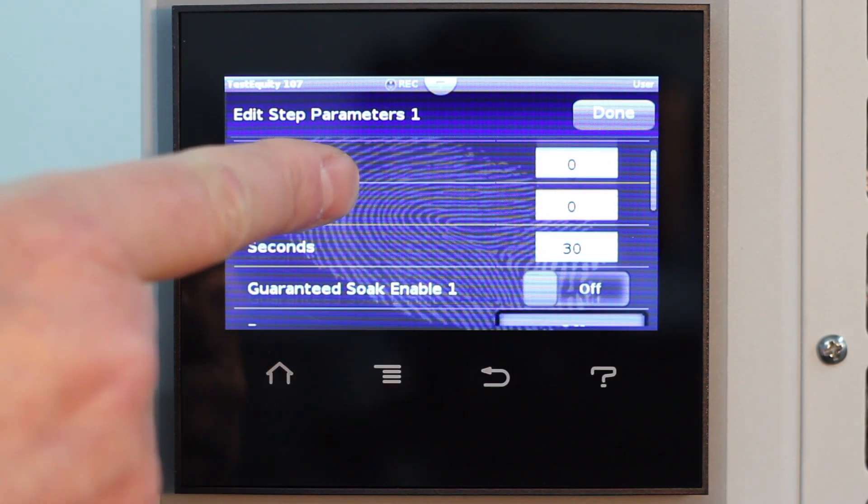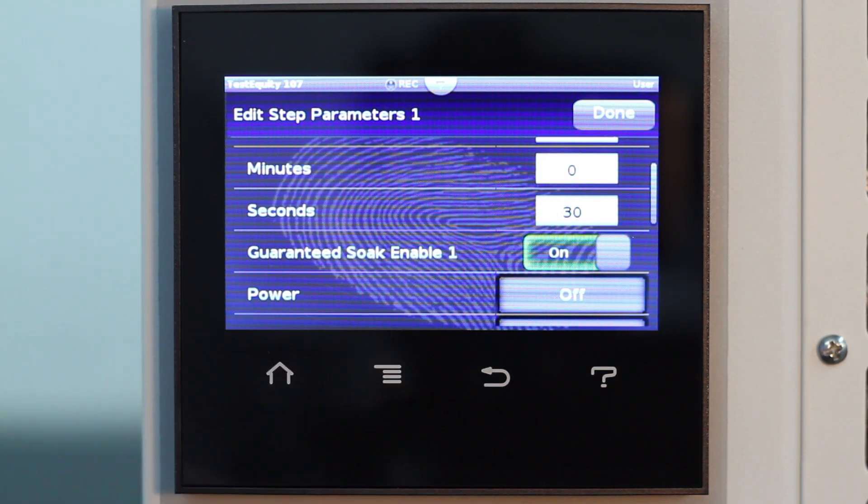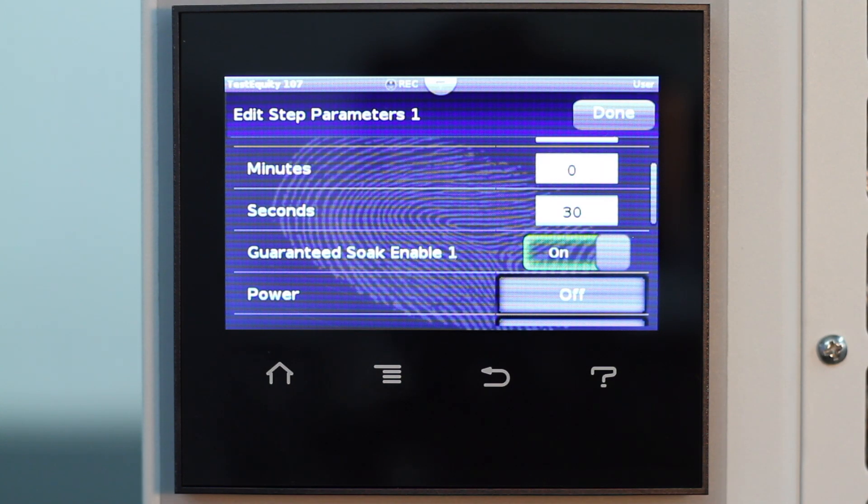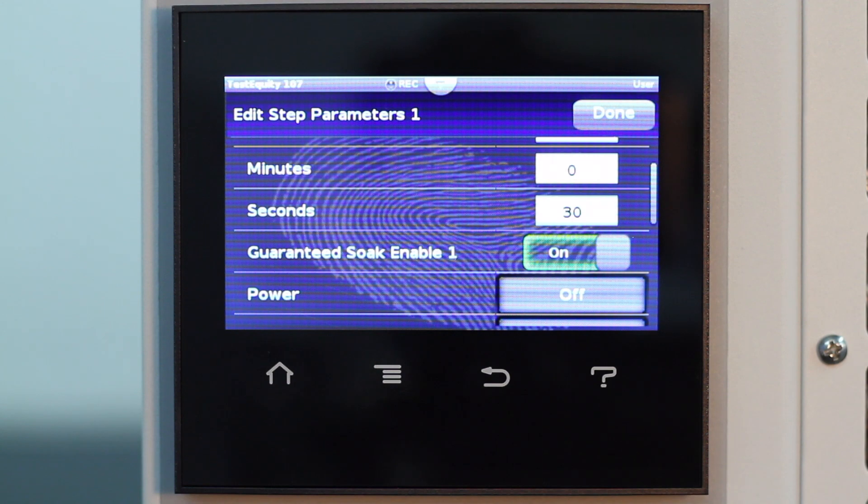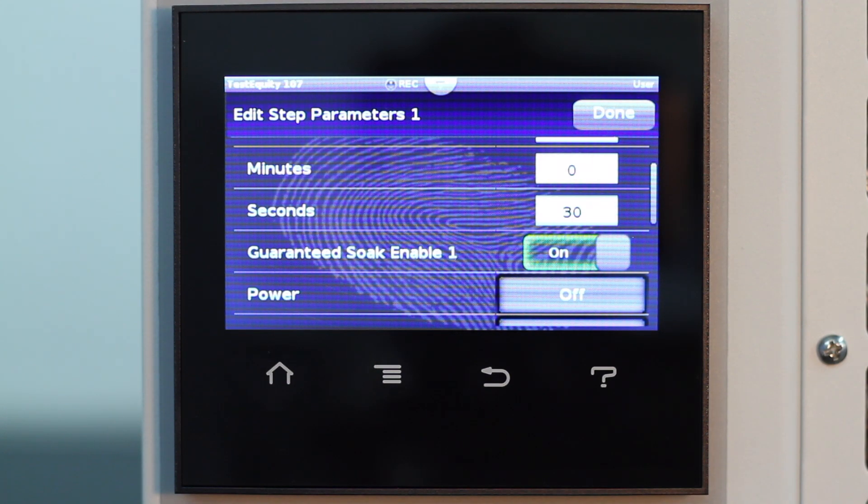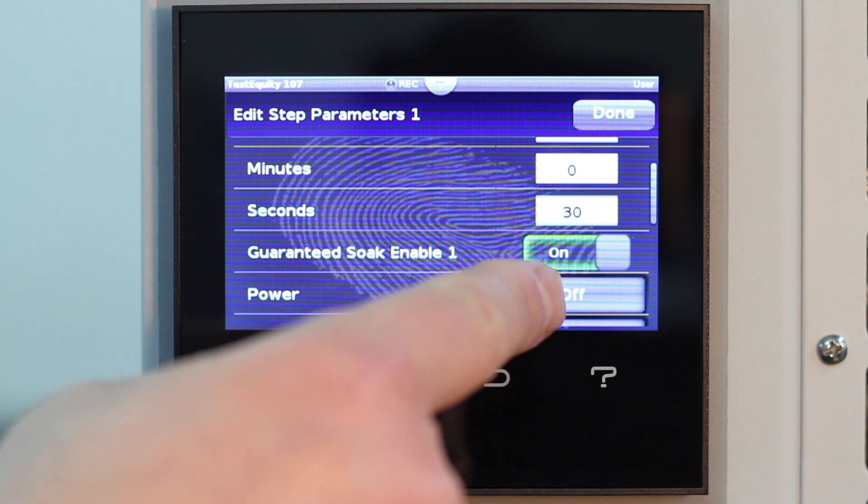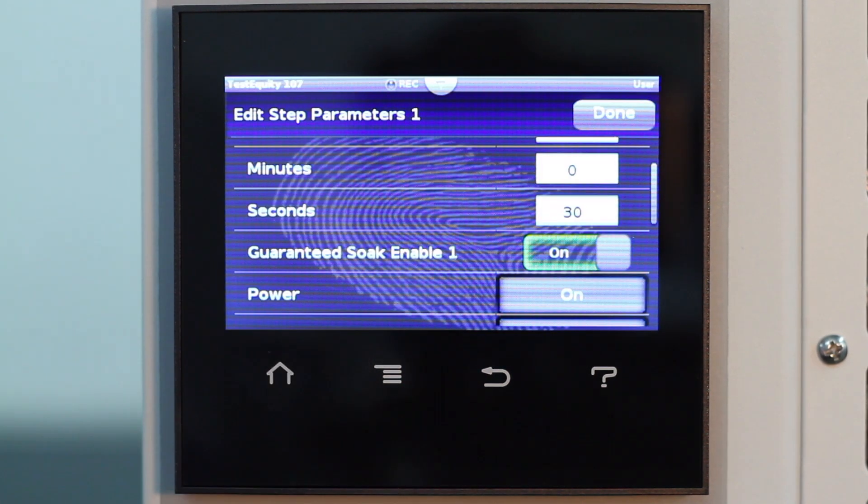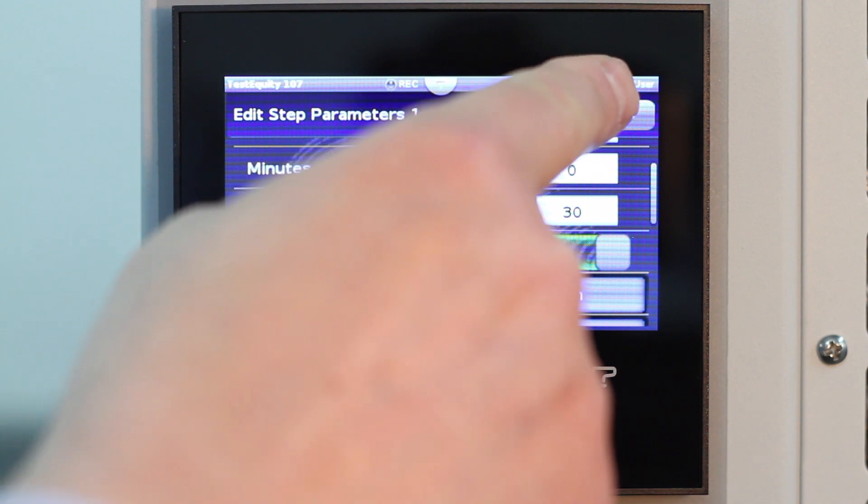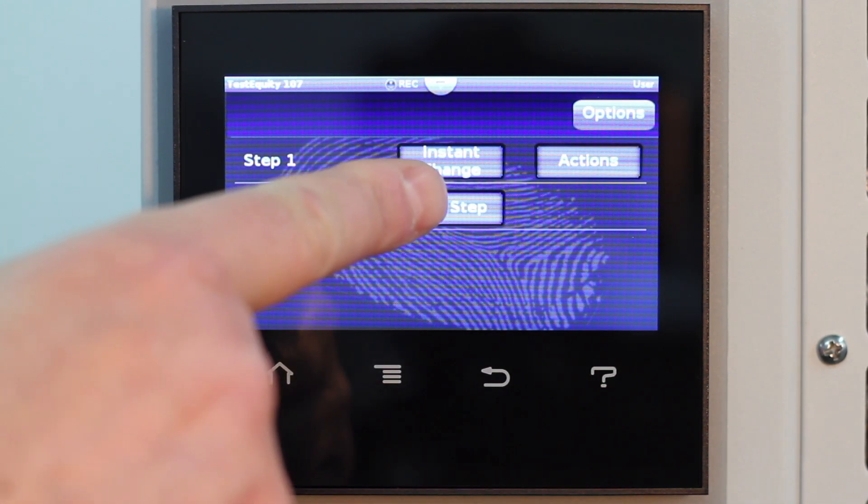Guaranteed soak enable is on because we do not want the profile to begin the 30 second timing until the chamber is within 1 degree of the target set point of 10 degrees C. Remember, 1 degree is the guaranteed soak deviation value we previously set. We want the chamber to be on, so select on at the power prompt. We are done with Step 1. Now we press Add Step to enter the next step.